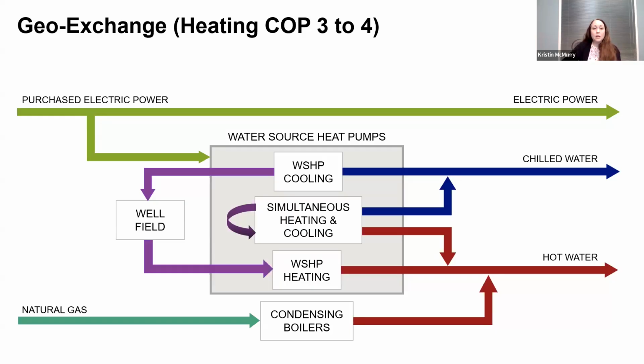You are going to store heat from the cooling side into your well field, and then later you can pull that out to use for the heating side and produce hot water. But you're also probably going to have to supplement that with something else — in this case, we used condensing boilers. And for the chilled water side, you might need additional chillers too, which aren't shown here, but could be part of your system as well.